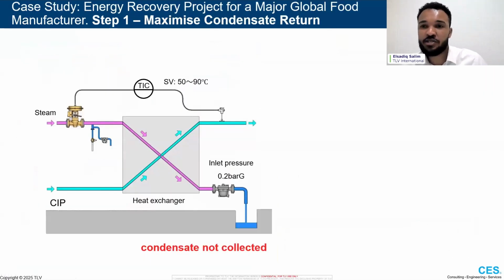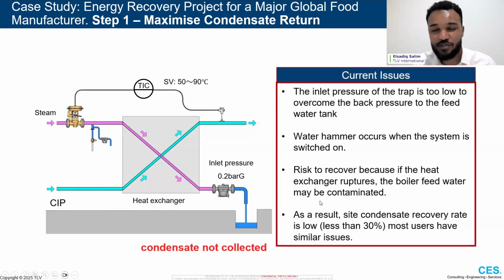So we're going to start with a case study. We've got 2 case studies today, both at the same site, a major global food manufacturer in the Australia, New Zealand region. This is very common across many sites at this kind of situation. So it's a general diagram, not an exact one. A general diagram where there's a steam heat exchanger, maybe for a CIP process, a clean in place process, where they're preheating that cleaning fluid with steam up to some set point between 50 to 90 degrees. And then very commonly, because that set point is less than 100, we get a situation where we have a very low pressure within the heat exchanger, and then the steam trap basically has a very low pressure going into it. And then typically that pressure is not enough to push that condensate all the way back to the boiler area.